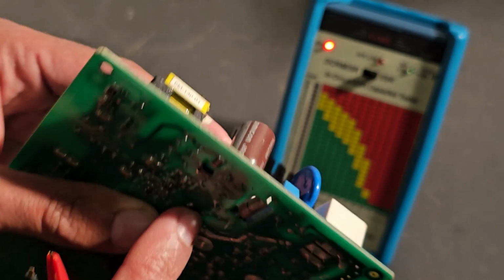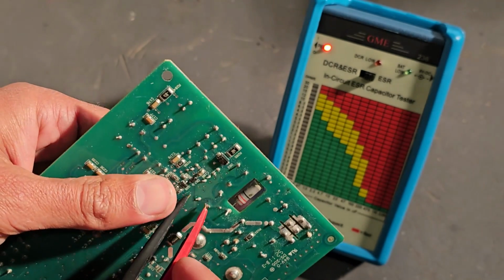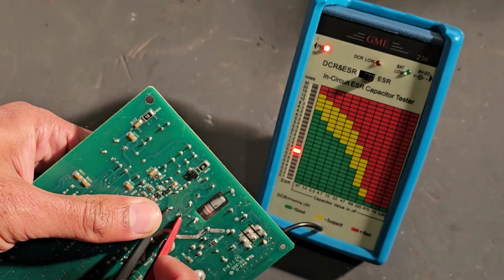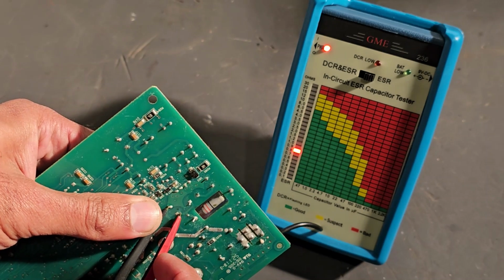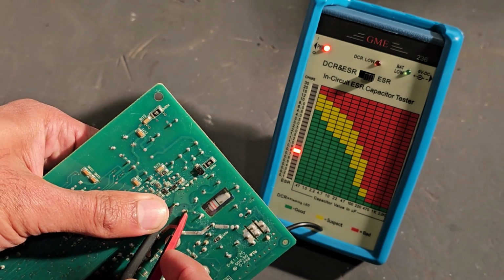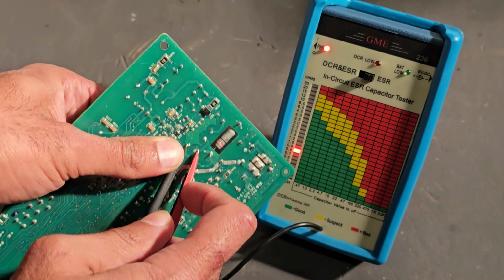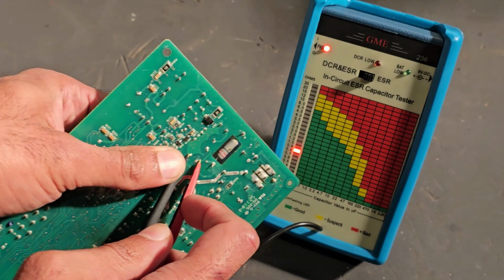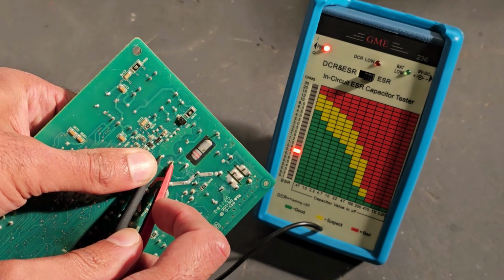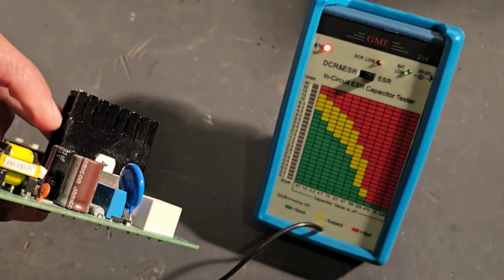So 22 microfarads. I believe the prongs are right here for it. Let's see. There we go. So it's giving us a rating of 0.8. So if we go from 0.8 and we scroll all the way to 22, we find that that's in the green range as well. So that capacitor is good.